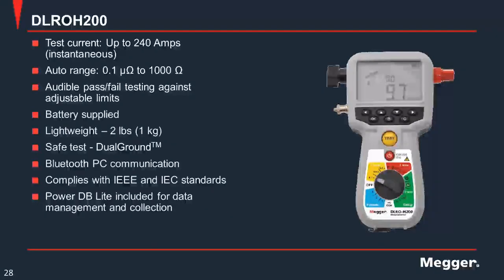If you need more current, you can use the DLRO 200 up to 240 amp with a resistance range of 0.1 micro ohm to 1000 ohm. It also has a capability for audible pass fail testing against an adjustable limit. Battery supply also has the dual ground method, complies with IEEE and IEC standards, and includes the PowerDB Lite for data management and collection. The difference between this equipment and the others is we cannot adjust the current. We can just set the current minimum 50 or 100 amp, but this device will inject and guarantee higher than 100 amp based on the IEC or ANSI standard.